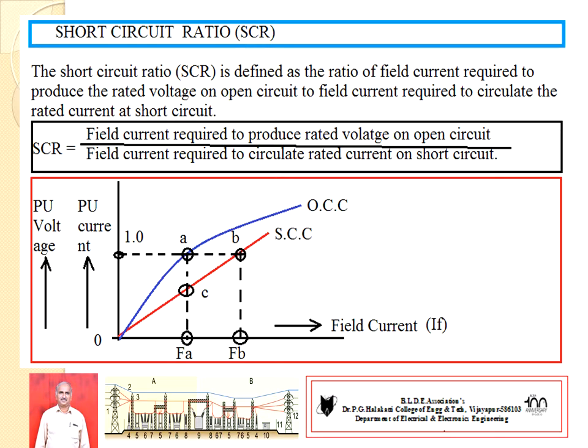By conducting the open circuit test and short circuit test, you plot the graph. From the definition: SCR equals the field current required to produce the rated voltage on open circuit, divided by the field current required to circulate rated current on short circuit. Refer to the diagram — OFA is the field current required to produce the rated voltage on open circuit, meaning the terminals of the alternator are kept open.